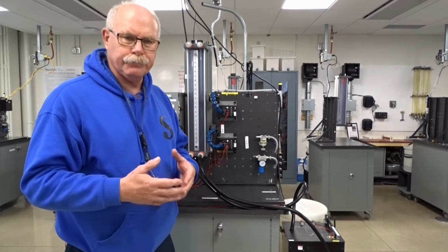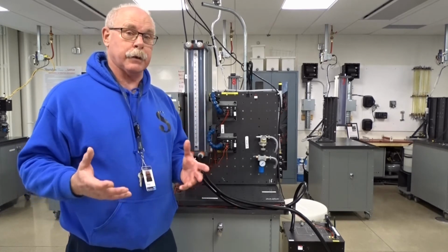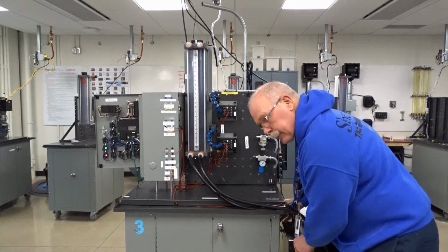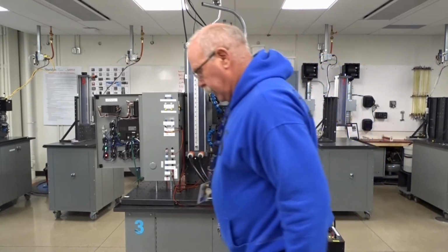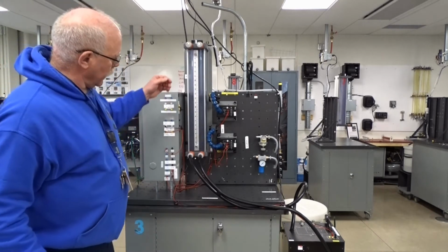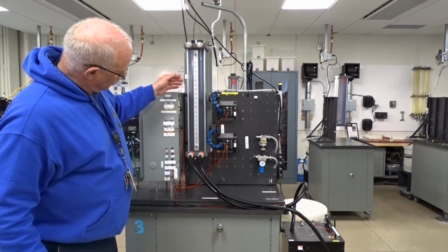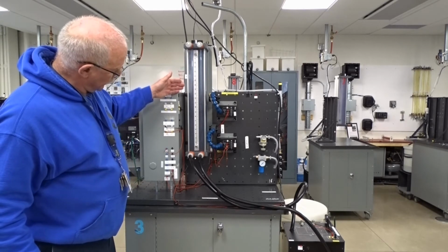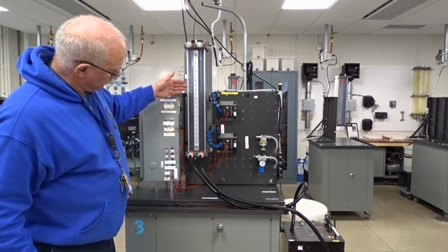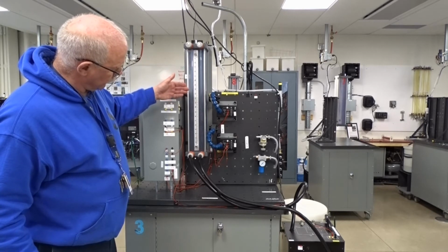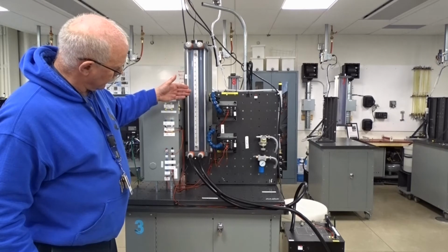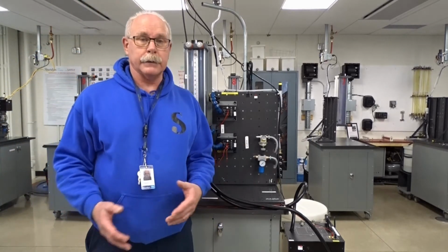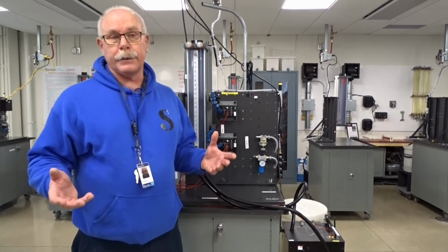I'm going to change the process. I'm going to put in a bit of a disturbance, and this disturbance is to restrict the amount of flow out of the tank. So I close one of the valves, and let's see if that has an effect on our dead time. 1001, 1002, 1003, 1004, 1005, 1006, 2007, 2008, 2009, 2010, 2011, 2012, 2013, 2014, 2015. About 15 seconds. What we have here is a 6-second difference in dead time.